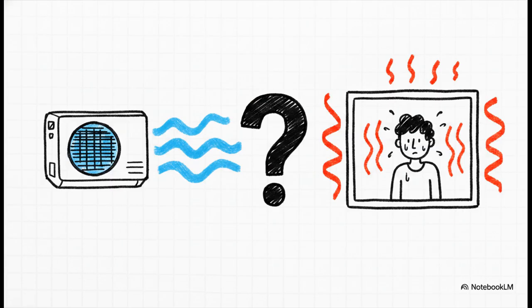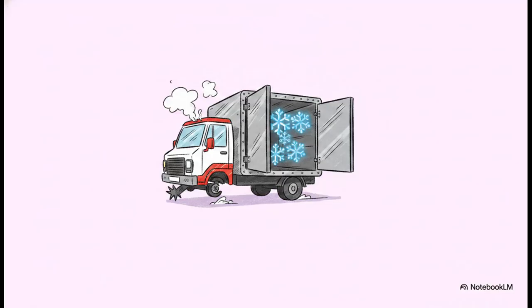All right, so what if the system is making cold air just fine, and the supply temperatures look completely normal at the unit, but certain rooms in your building still feel like a total sauna? This brings us to culprit number 3, and surprisingly, it has absolutely nothing to do with the refrigeration itself. Think of airflow like a delivery truck. If the refrigeration system successfully creates the cold air, but the ductwork, our delivery truck, breaks down along the route, well, the cooling simply never reaches you. The destination remains hot and you remain miserable, even while the equipment is running continuously up on the roof, just trying to compensate for the problem.